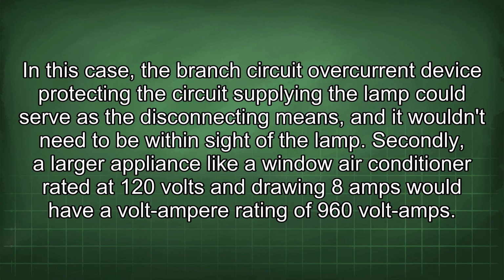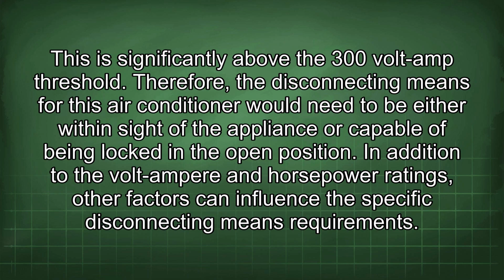Secondly, a larger appliance like a window air conditioner rated at 120 volts and drawing 8 amps would have a volt-ampere rating of 960 volt-amps. This is significantly above the 300 volt-amp threshold. Therefore, the disconnecting means for this air conditioner would need to be either within sight of the appliance or capable of being locked in the open position.